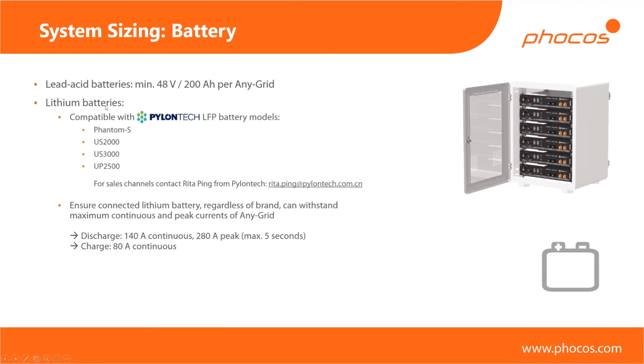If you're using lithium batteries, then typically you will have ratings for how many amps of charging and discharging current are allowed on the batteries, so you can check that and make sure it's compatible. As a reference here, the maximum charging current is 80 amps, regardless of whether it's PV, grid, or mixed. Again, you saw before, we can reduce that charging current if you need to cater towards smaller batteries.